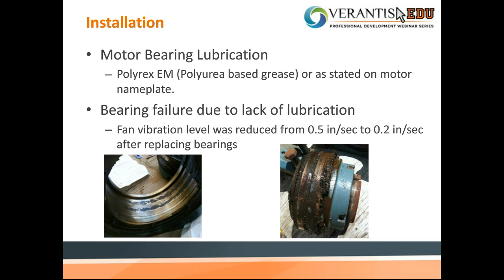Bearing failures due to lack of lubrication, we have seen that before, and we've seen it a lot. And if a fan is installed on the rooftop, you may not have the proper maintenance plan for it. So what happens? The fan stops running or starts vibrating. Why does it vibrate? Because there's a failure due to lack of lubrication within the fan. So just by adding lubrication to a bearing, the level is reduced from 0.5 inches a second to 0.2 inches a second after replacing the bearings. So definitely the bearing failure can happen if not properly maintained.